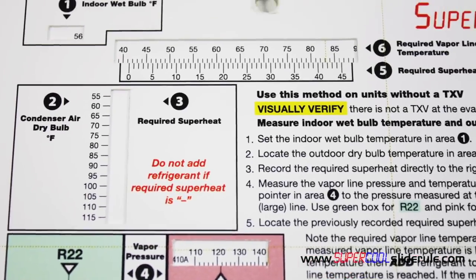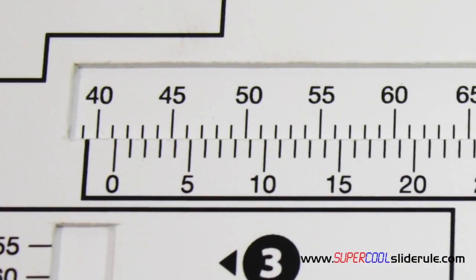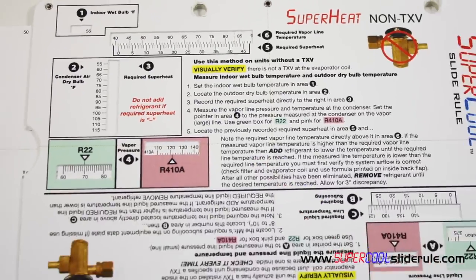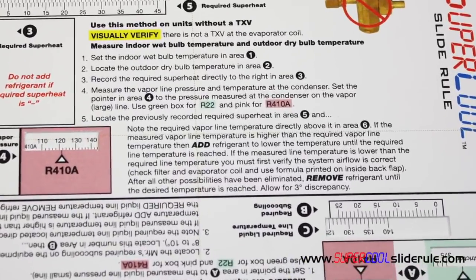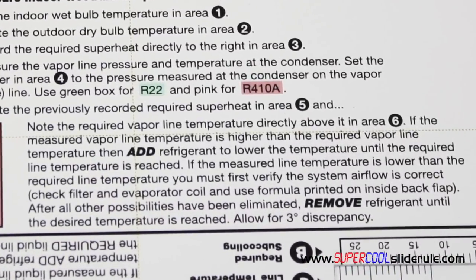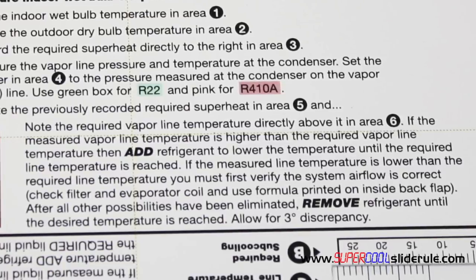We then proceed to box 5 and locate our previously recorded required superheat, which, if you recall, was 9. Directly above the 9-degree mark here is 50. So 50 degrees is our required vapor line temperature. Measure the vapor line temperature. If the temperature is higher than 50 degrees, add refrigerant until you reach 50 degrees.